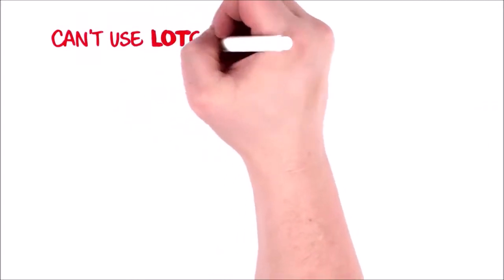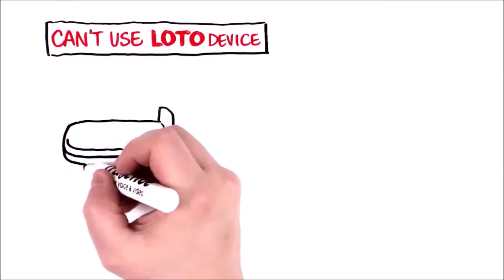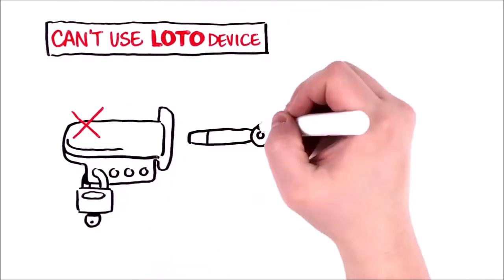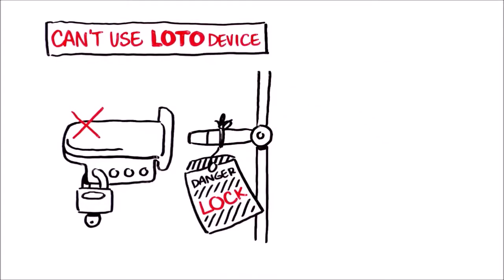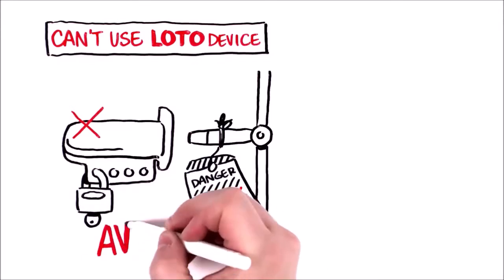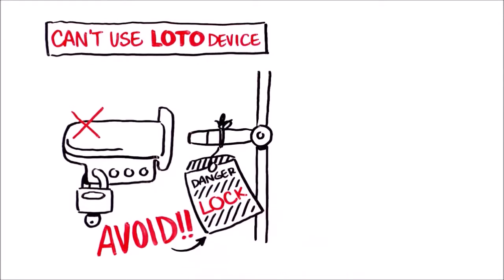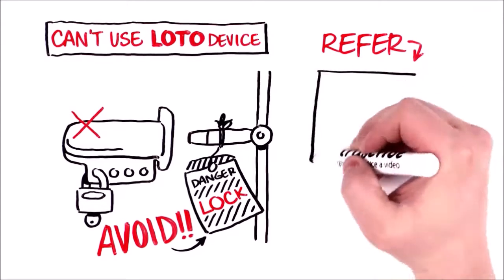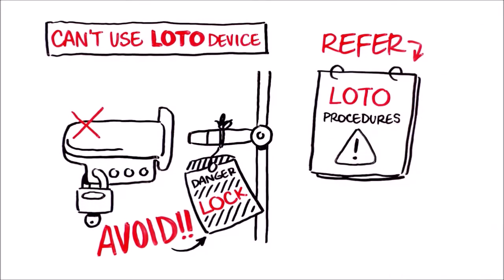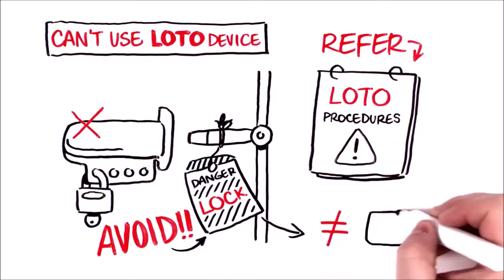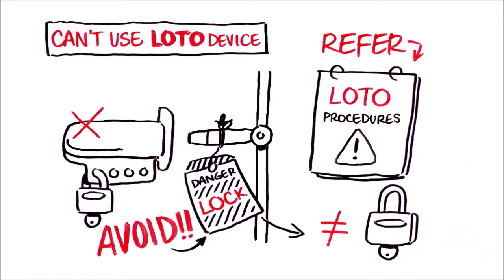What should you do if you can't use a lockout device during your service activity? Can you use just a tag to notify people not to reactivate an energy source? Only if that is the sole option. In other words, this scenario should be avoided as much as possible. If it is the only option, refer to your site's LOTO procedure and take special safety precautions. Remember, tags don't provide a physical barrier against reactivation, which severely limits their effectiveness.